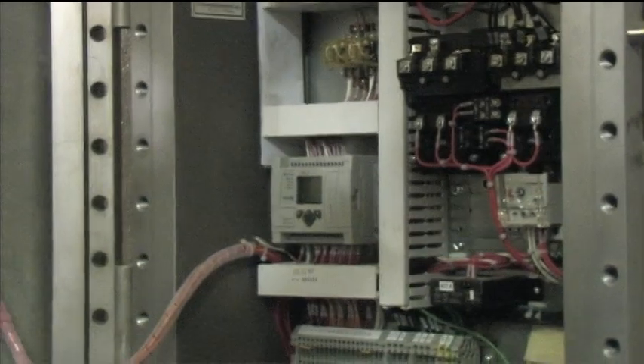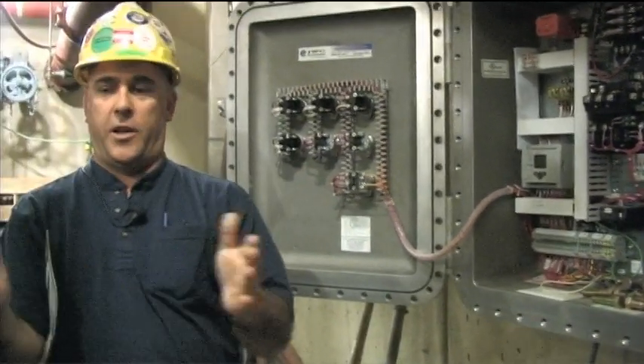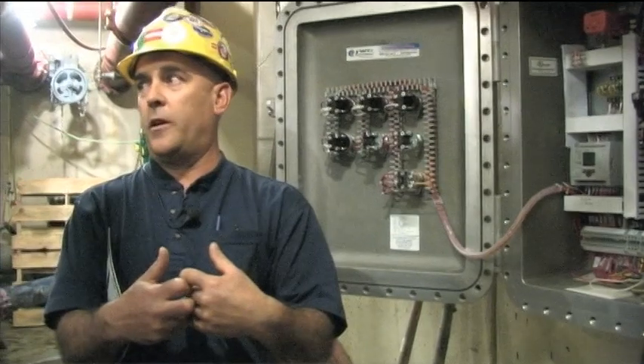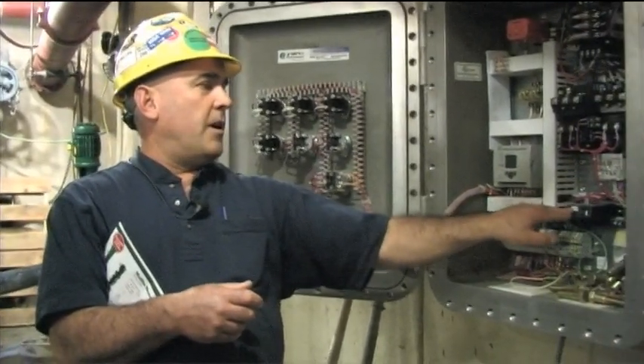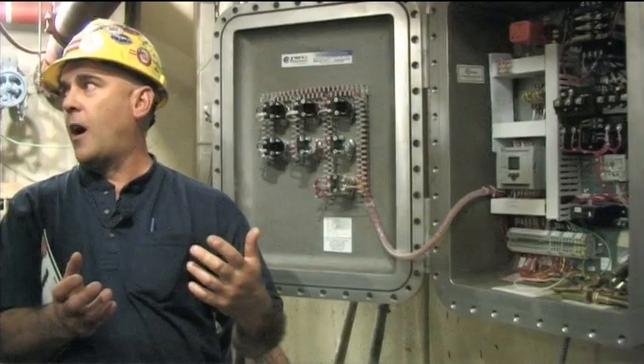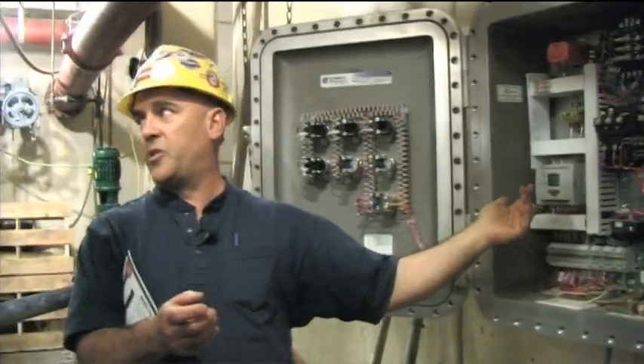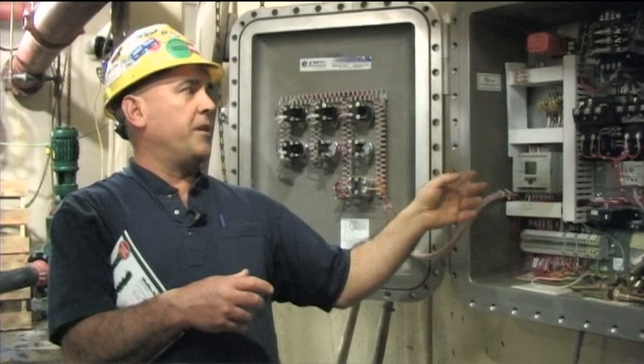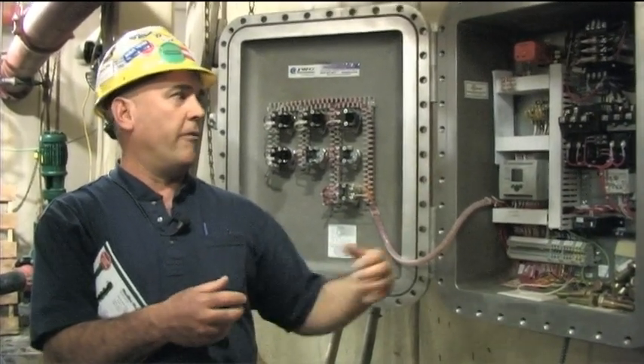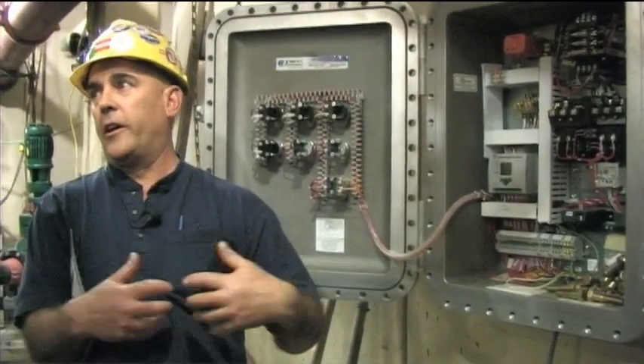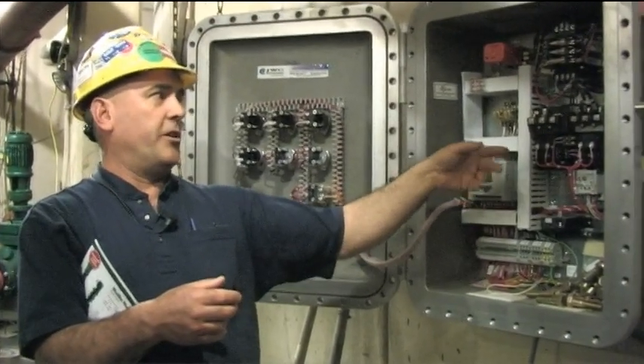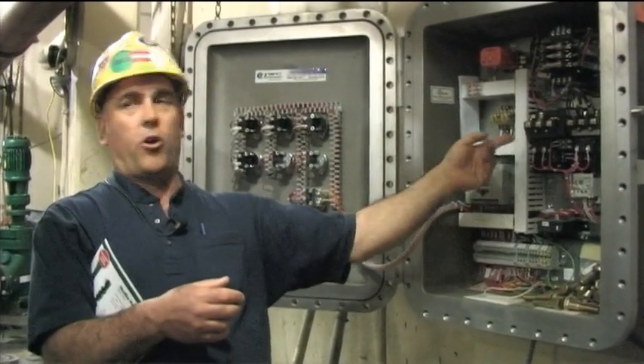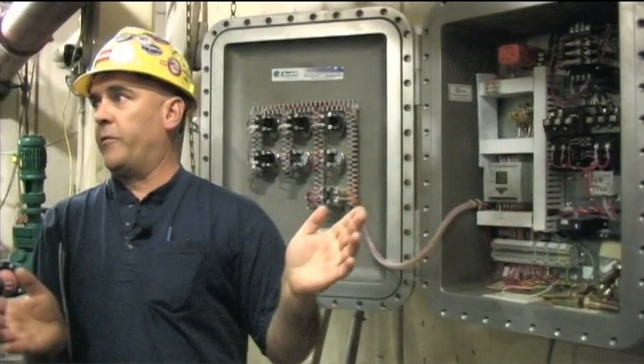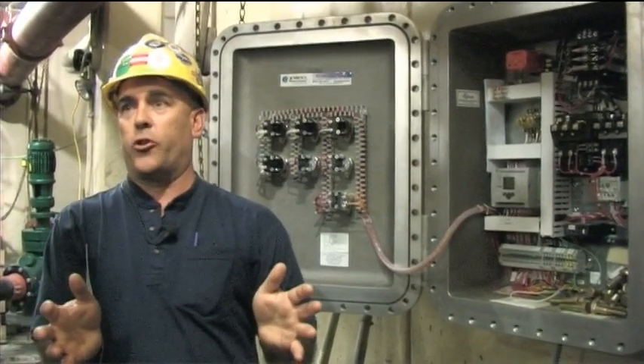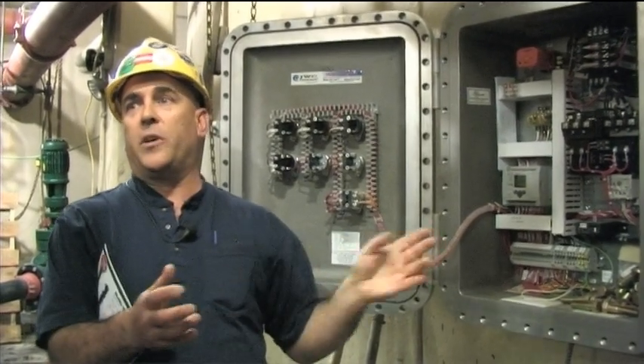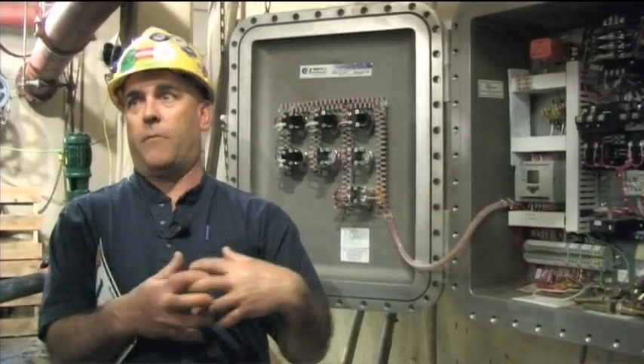Under normal operation, if you get a jam, those cutters are rotating towards the center and you get something jammed in there. The current sensor will sense that spike in current and send a signal to the PLC. So it's running in forward now. What it does is it senses that high current and it wants to reverse it to try to clear it. So it sends a signal and it's just switching 2 of the legs from one contactor to the other and having it go in reverse. It just goes in reverse for about 1/4 of a turn, and then it'll come forward again. The PLC tells it to go back to the other contactor and come forward.